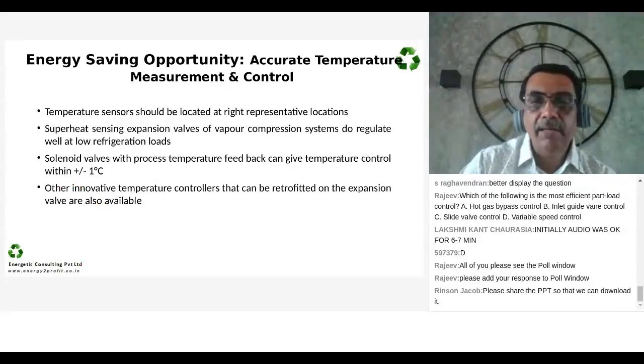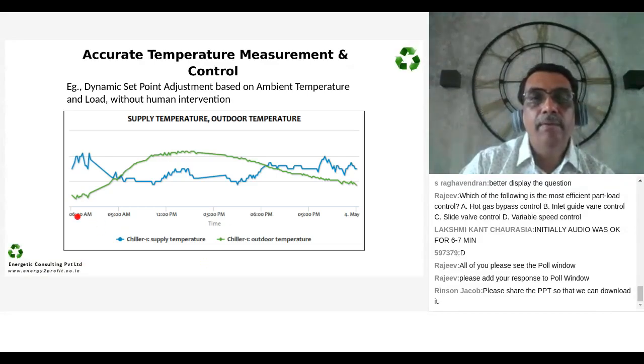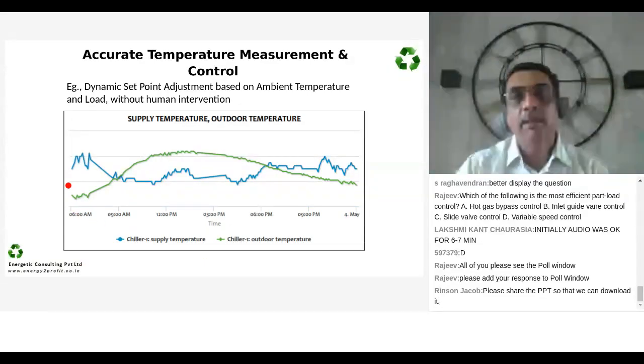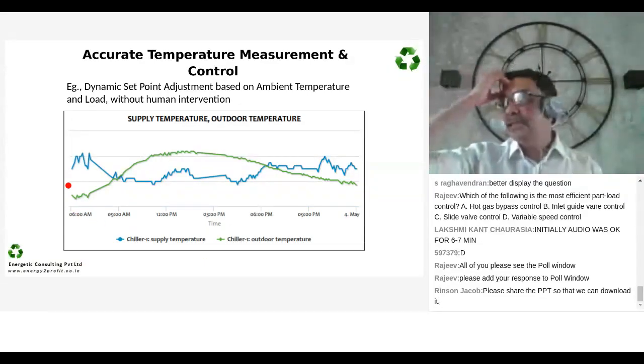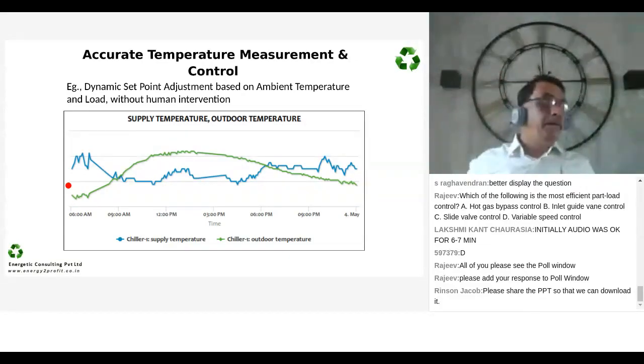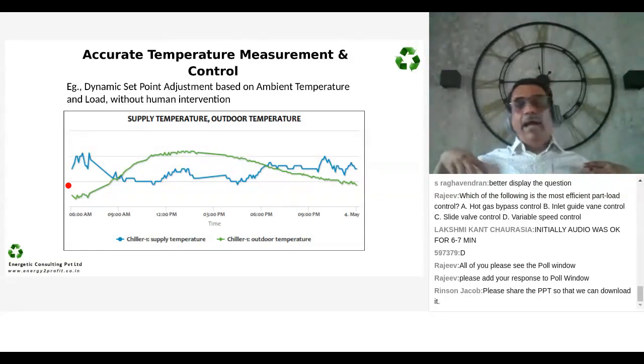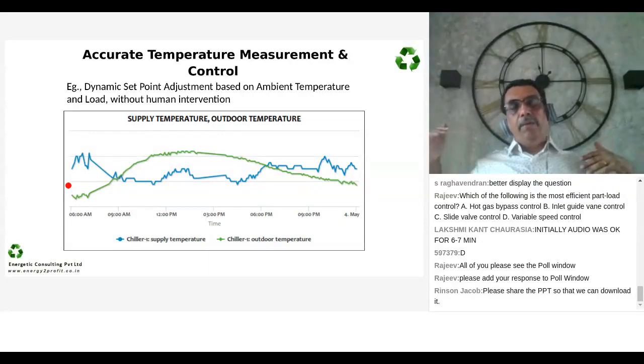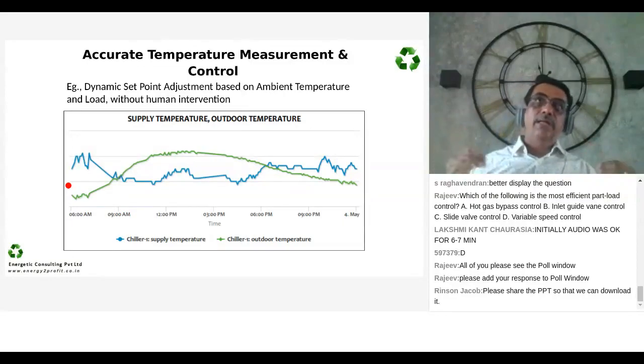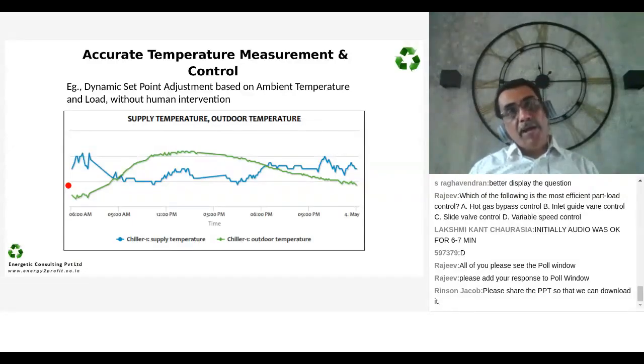You have an innovative temperature controller which monitors the supply temperature based on the outdoor temperature conditions. Say, for example, you are in an air-conditioned auditorium or your office. Now, when the outdoor temperatures are going low, obviously you do not need to maintain the same chilled water temperature to get comfortable air temperature. Why? Because load has reduced.